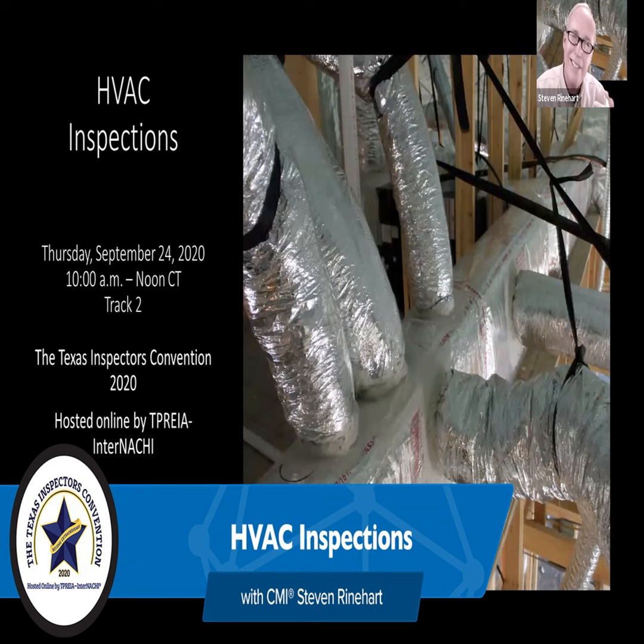I peek in the return grill under a deck, just to look how much stuff is down there. And if I see a pipe, a lot of times you'll see the condensation go down and you'll see another quarter inch copper or plastic that comes up out of the deck and heads up through the ceiling. That's a clue. But yeah, you should note presence of a condensation pump.